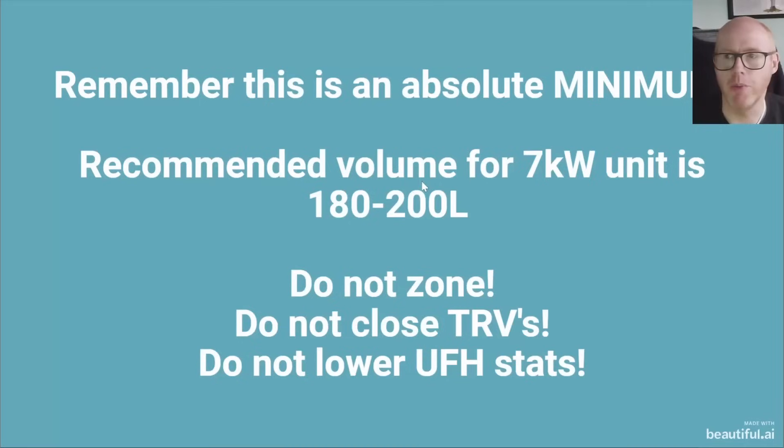The actual recommended volume for the best operation for a 7 kilowatt unit is closer to 180 to 200 litres. So three to four times the minimum required amount for a Vaillant heat pump is what you really need for it to work really well, and that can really help with defrost.